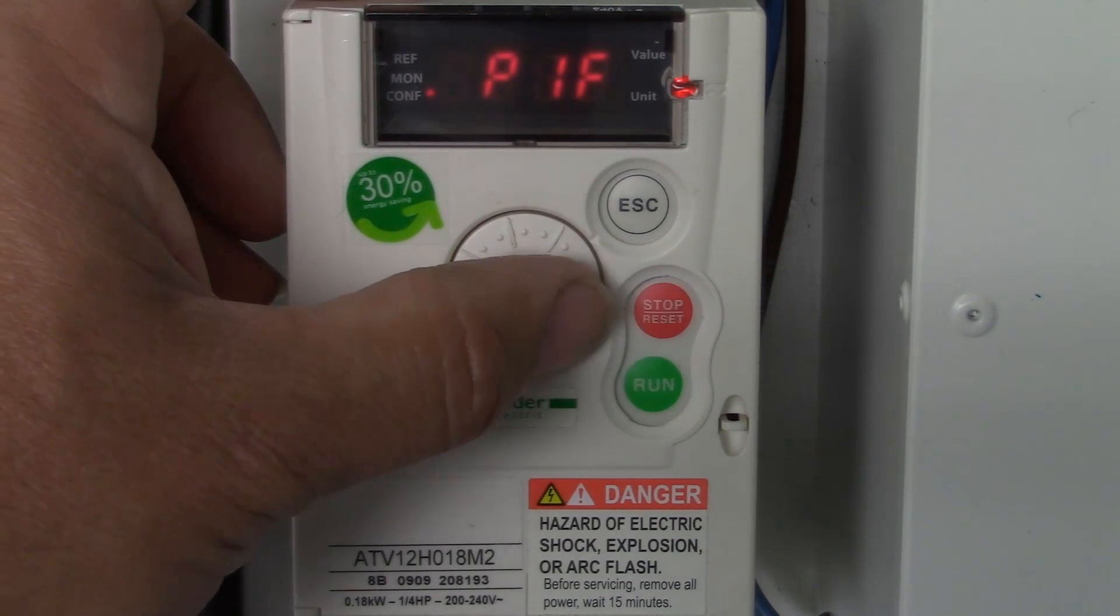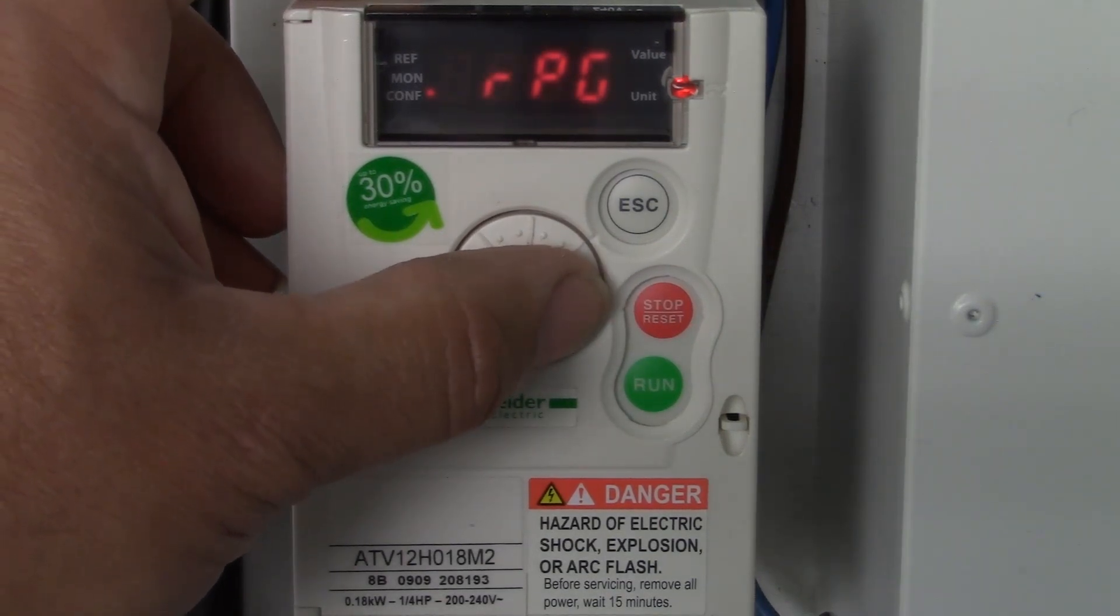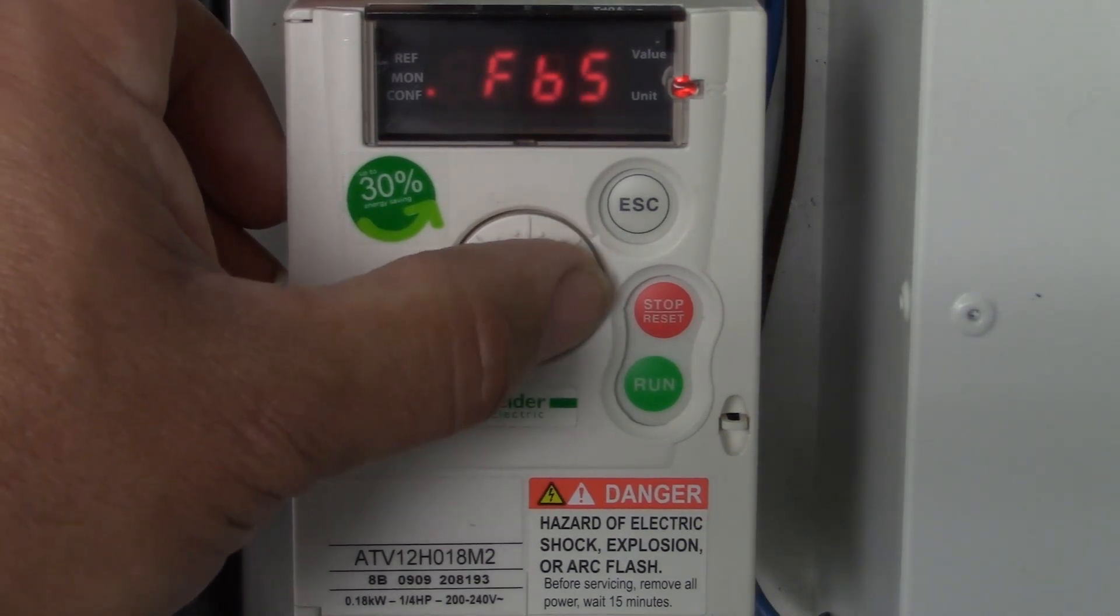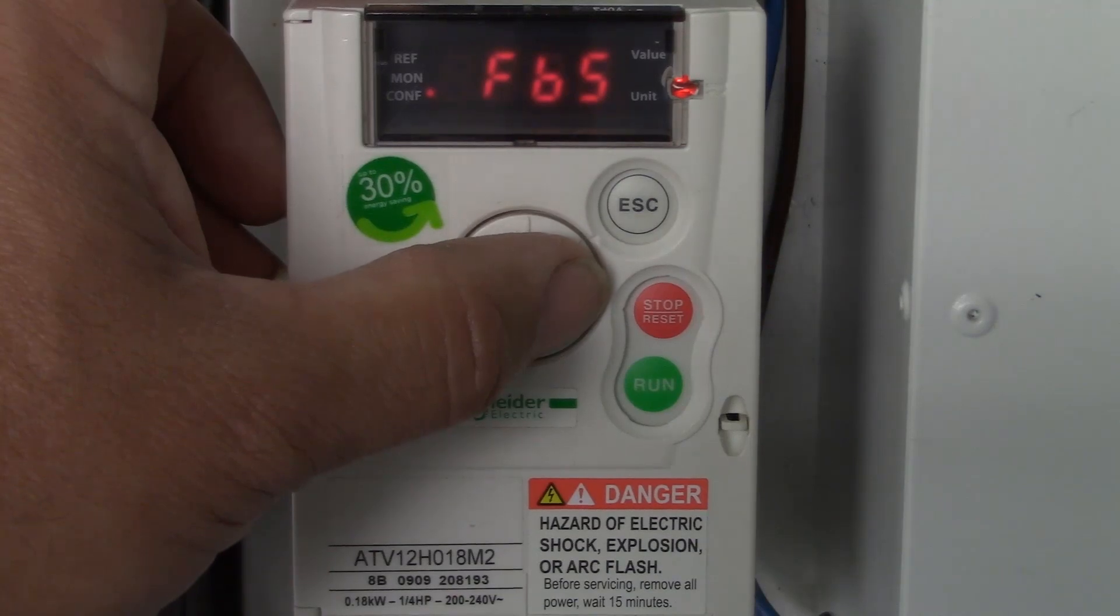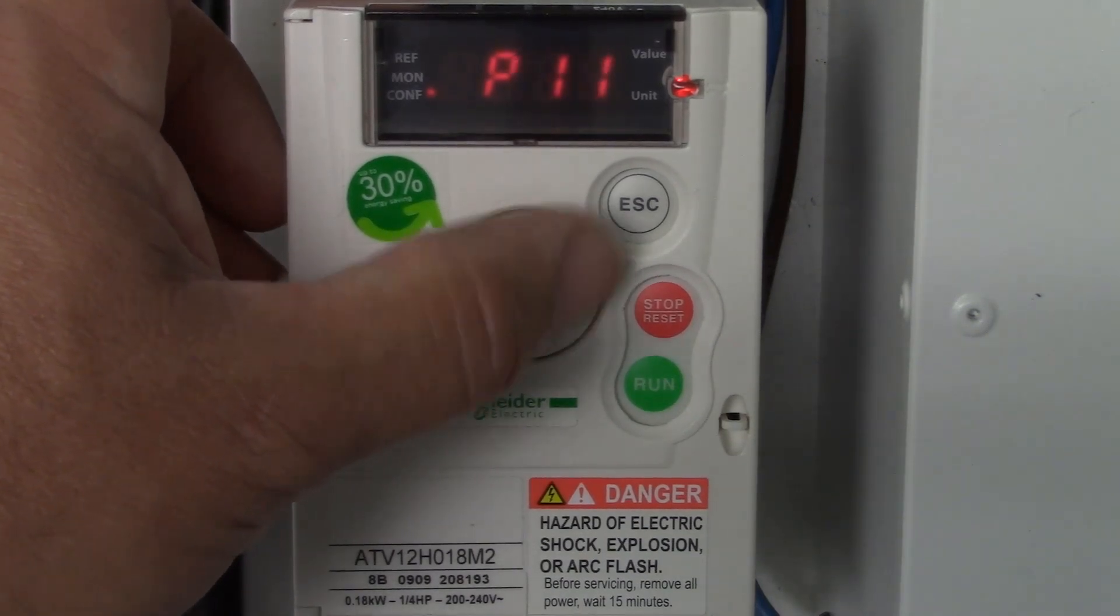Just below the PIF parameter we have the RPG, RIG and RDG and FBS. These are your gains inside the drive. Do not adjust these. Leave these at default settings until you have carried out your first system tests.